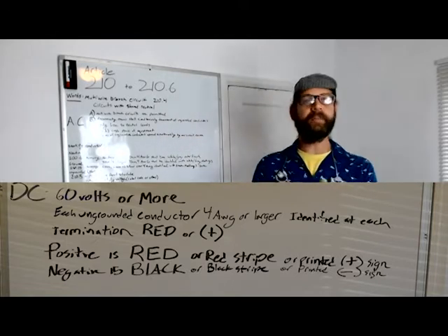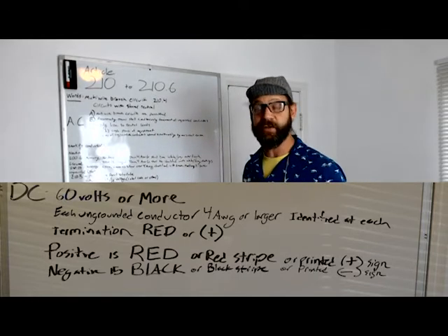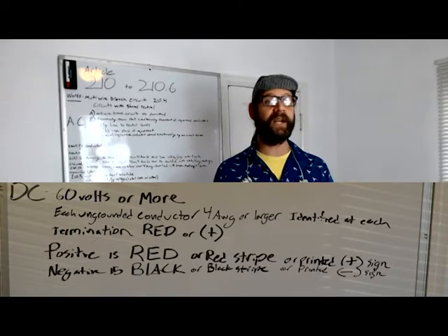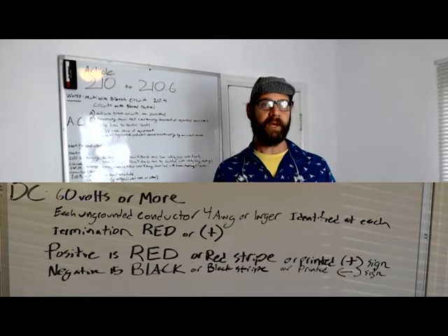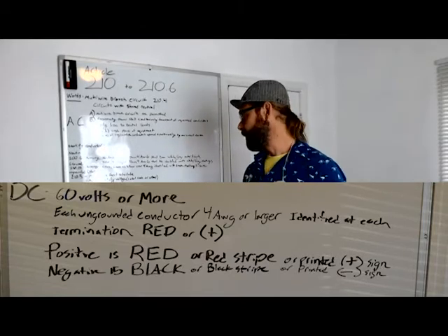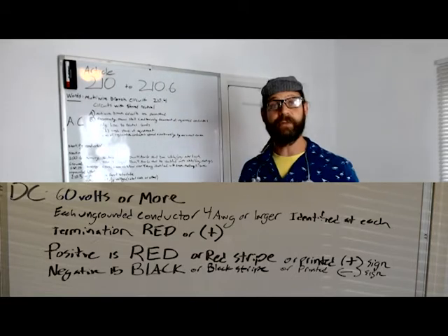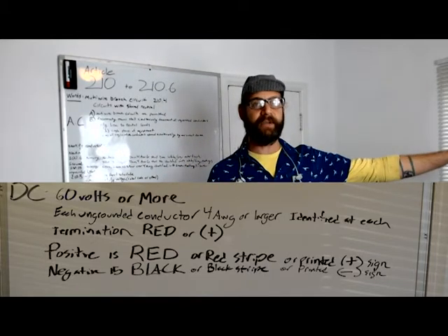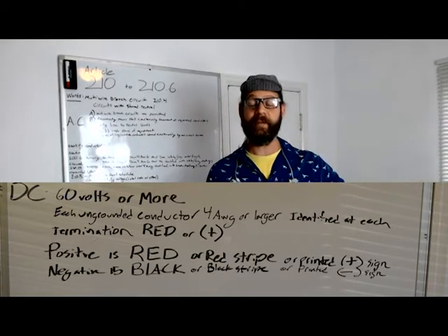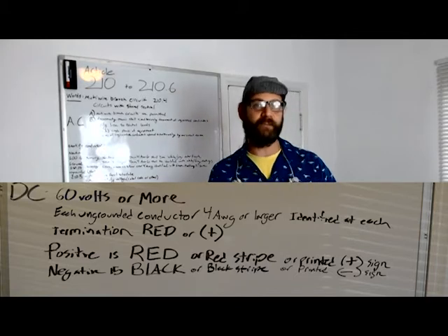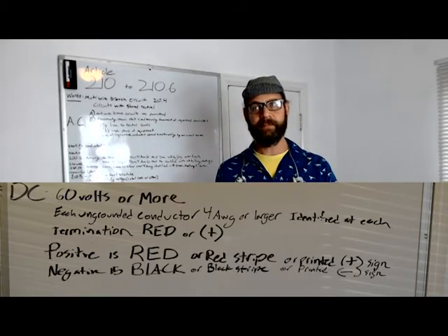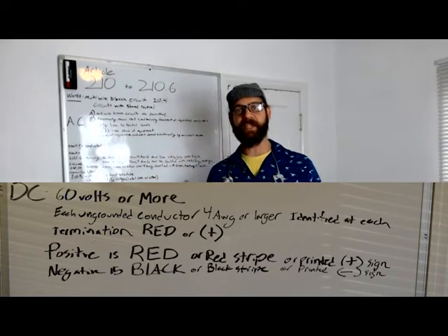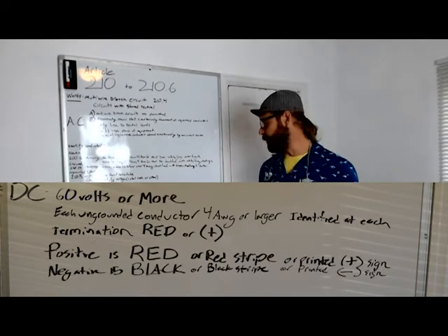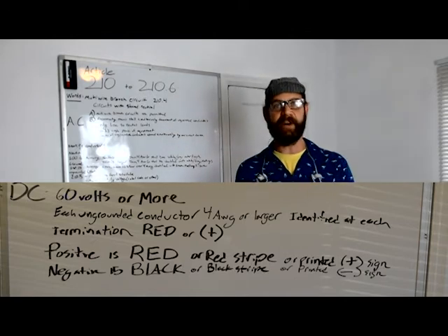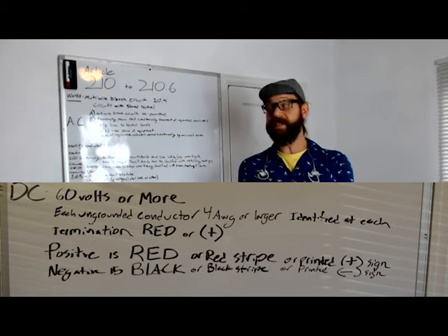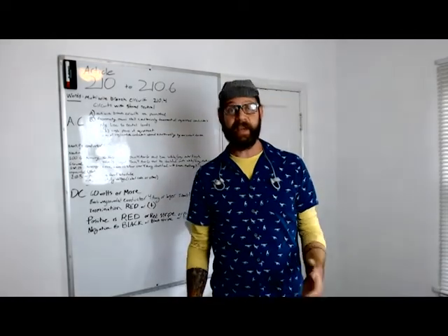And the reason they do this is they want to give you a little bit of leeway. Once you've used all the red wires that you can and all the black wires you can, you are going to want to keep some things separate. It's really easy to order this stuff. According to this code section, you run DC, you get a yellow wire with a red stripe. That red stripe means it's positive. You get a yellow wire with a black stripe, black is negative. You could say all the DC power that goes out to that branch is all yellow, and you'll know whether it's positive or negative because it has a red stripe or a black stripe. So that's why it's not just black and red. You can have any color conductor with a black stripe, except red, or any color with a red stripe, except black, and that'll be positive and negative. It's very common in equipment that comes out to the field to have this printed shrink tube positive, negative on it. So that's why they put that in the code. So that is essentially Article 210 through 210.6. And come back, we'll do 210.6 and up.